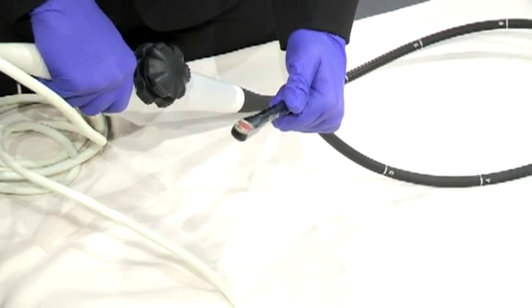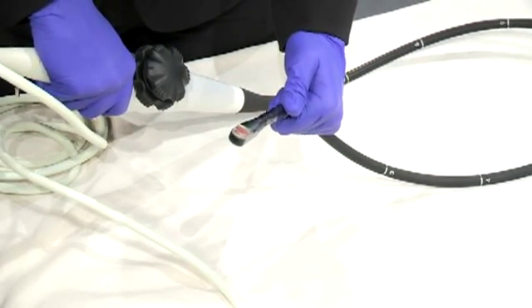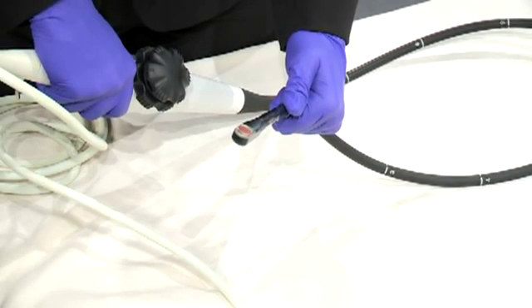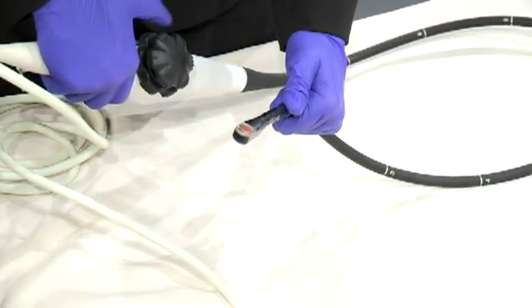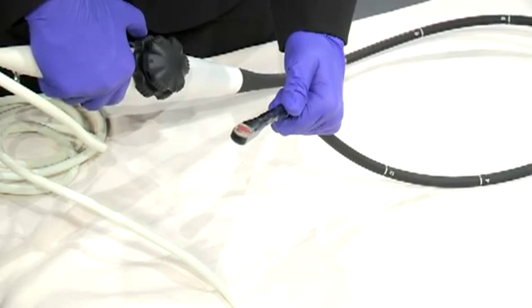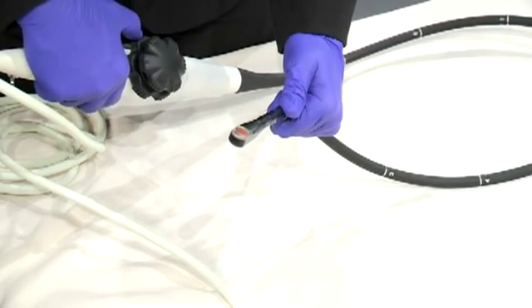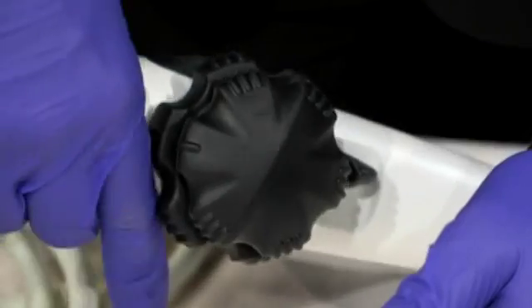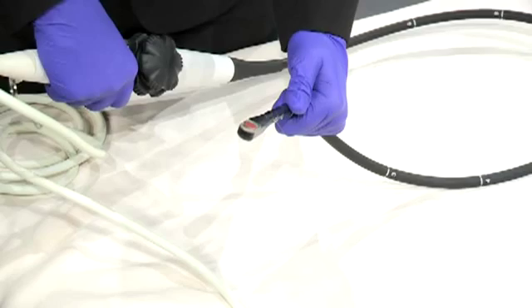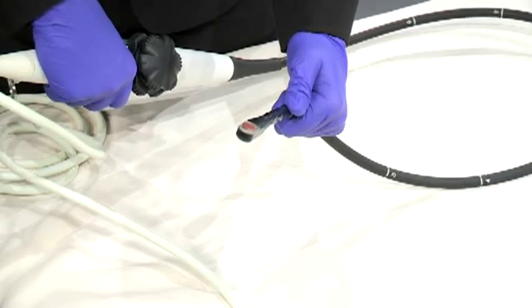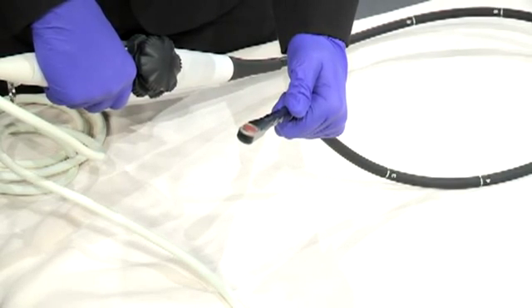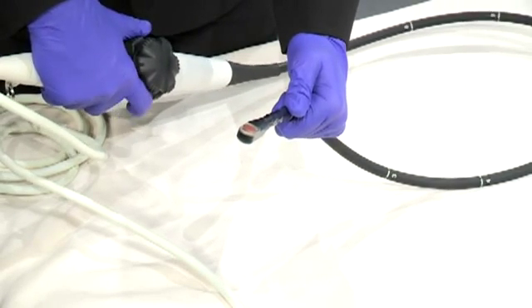Let's now take an opportunity to review some of the probe operations. The TEE probe endoscope has two wheel controls for deflection of the distal tip of the transducer. The deflection wheels control up and down and left and right tip deflection. During this demonstration, we will reference and orient the endoscope with the control wheels up. Operating the lower wheel controls.